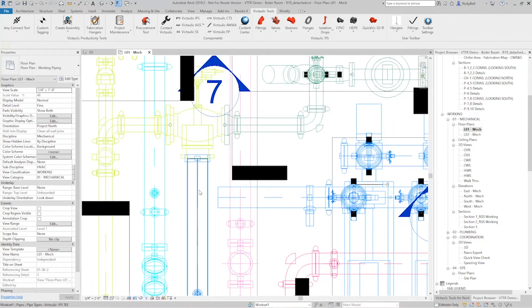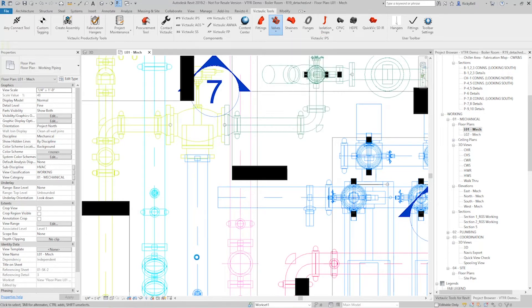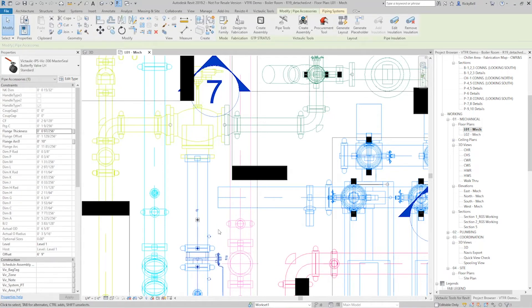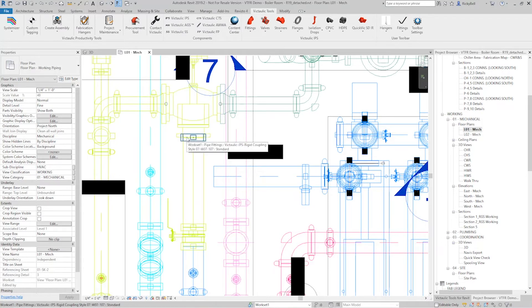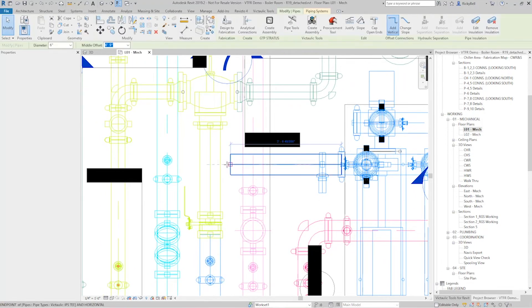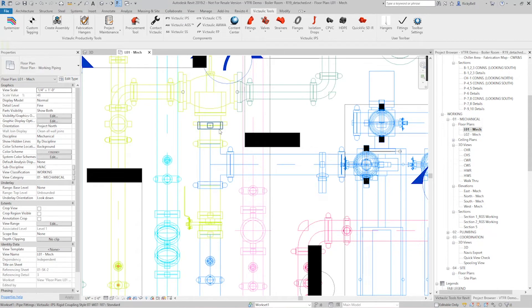However, if I'm not quite done with this system and things need to change — maybe I need to put in a valve at the bottom — here I have my valve. I can rotate it, but actually I want to flip that valve around. When I flipped my valve, Revit improperly applied the system. It regenerated a portion of the pipe and then saw a system that was attached and said, well, you must be a part of this. So obviously that's not correct. What I want to do is redefine some of this as chilled water supply. I could finish off and connect in a T here, and it's going to get a little crazy. But once I have it closer to where I need it to be, I'll select that coupling and switch it out with a flange.